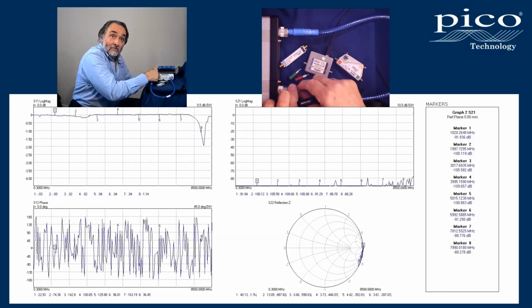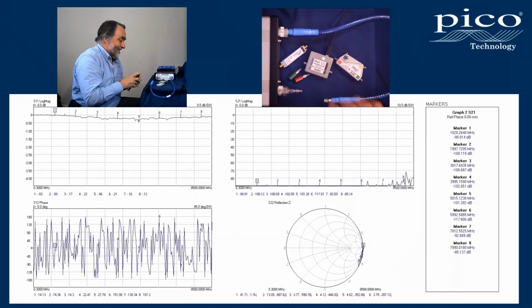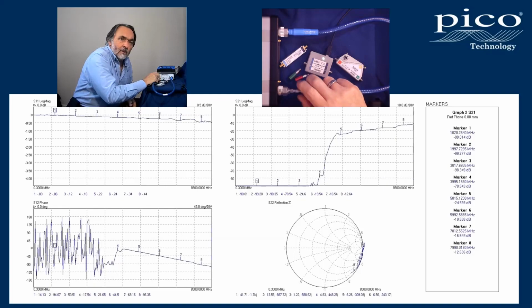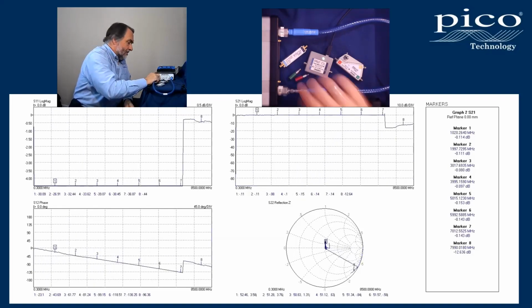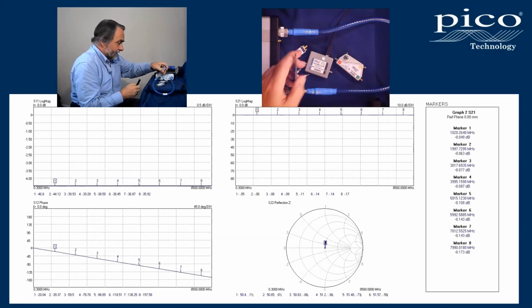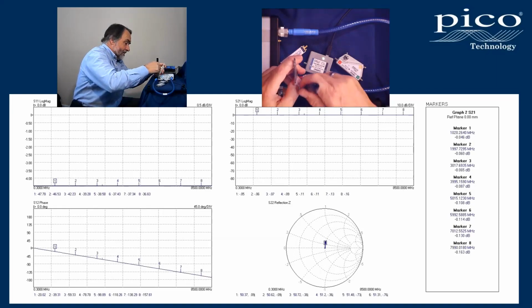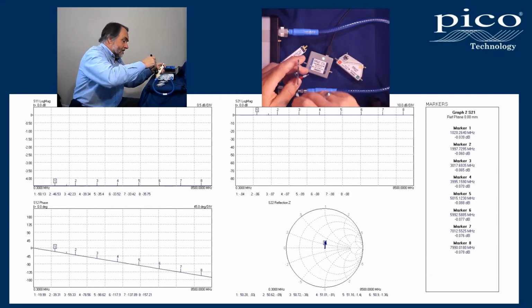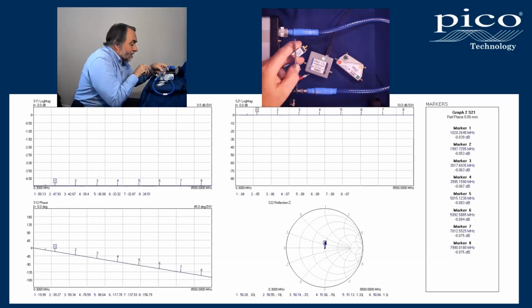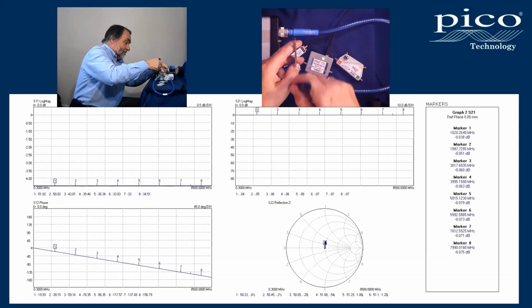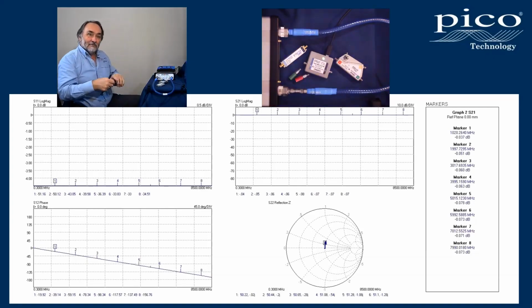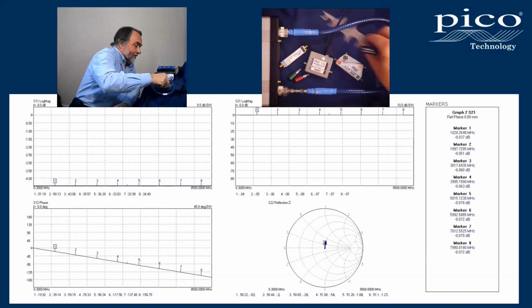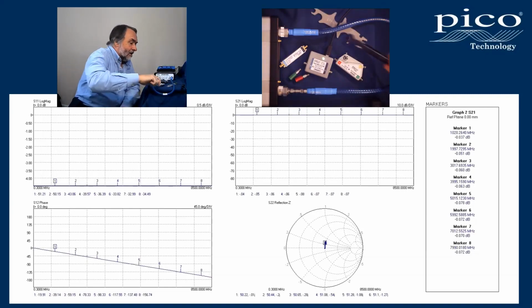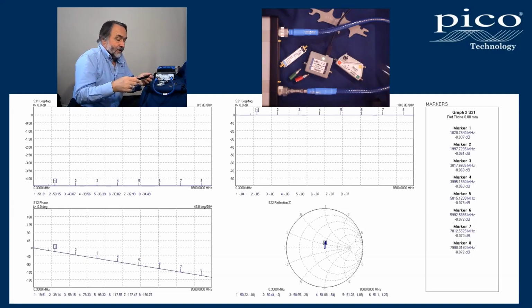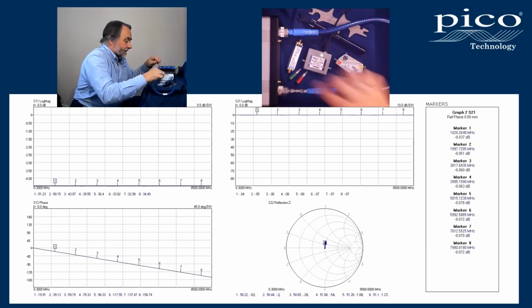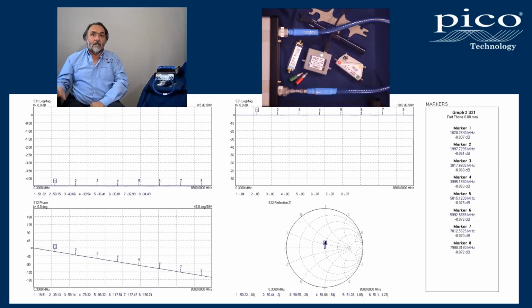Now, I'm going to be honest with you, this through is not marked. It's not marked in the sense of the polarity that was used when it was calibrated. So the data I have for this through, it's uncertain what the polarity is. So in practice here, I have to make two measurements and then compare the best ones, which we would deem to be when I've got the polarity of my data and the polarity of the reference data the same. So that's what I do in practice.